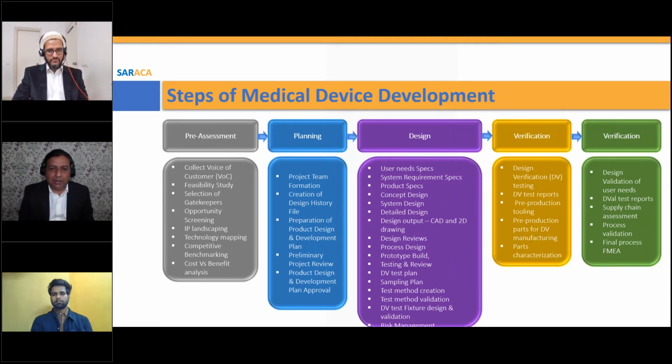I would like to just add one point here. As you pointed out, risk management is in the design phase, and as you rightly said, it depends on your quality management system. Many companies are starting risk management as early as possible. But what we have seen recently, as we do a lot of reviews of our customers' design files and risk management files, is that the new standard of risk management, ISO 14971 2019 version, has very critical elements.